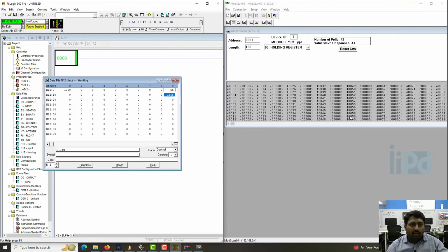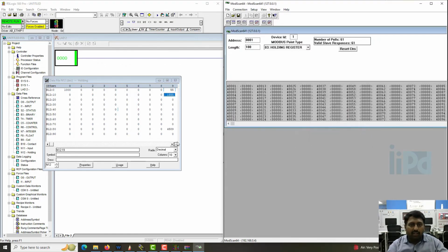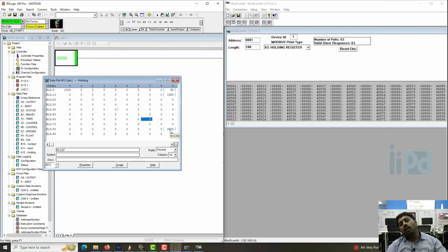So if I am writing from 40100, 401, okay, let's say 400090. So it will update here as, okay, let's say I want 4568. So 4589 update. You can see it updated as 4589. So now our MicroLogix 1400 PLC is working as a Modbus slave or a Modbus server. Okay, so in 485 it will be a slave, but in Modbus TCP this is now acting as a server.